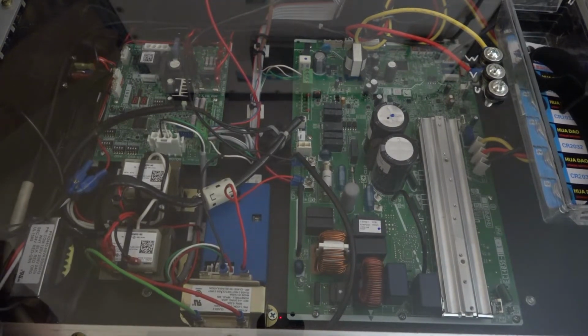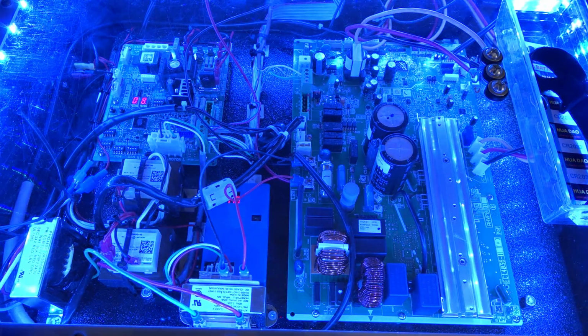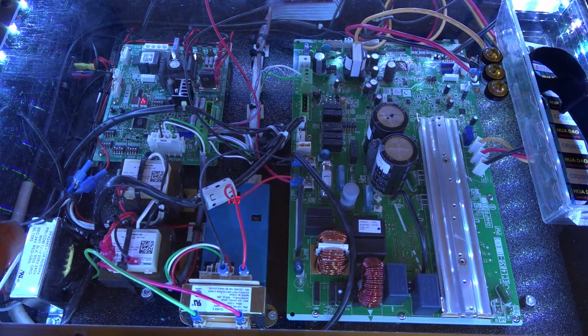Now some of the things we've done here, I've also added in some resistors to simulate certain temperatures, like a thermistor inside the system. We've added some LEDs in here to be able to turn this thing on and light it up so you can see it as you're working on it. I'm in the process of adding all of the pressure transducers, having a complete working model here with EEV valves, the whole nine yards. But I've got my COM plug here to simulate all of the things inside the board as far as voltage I need to be able to test and make sure that I've got a good stable COM bus in the system.